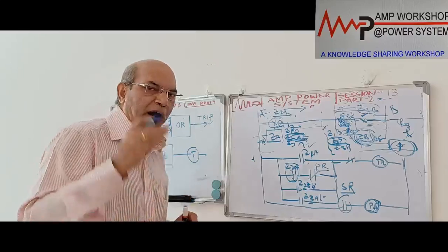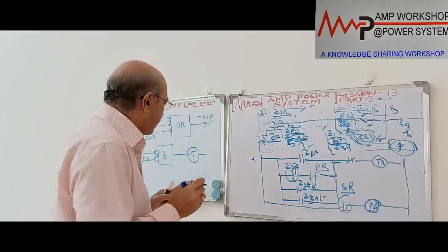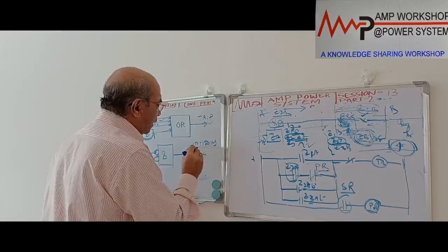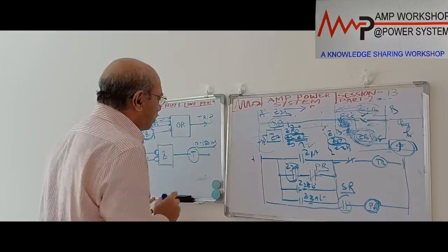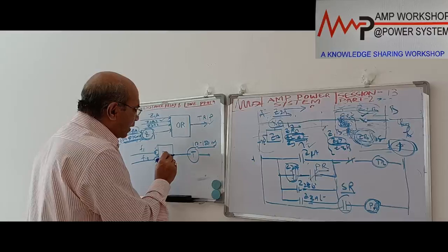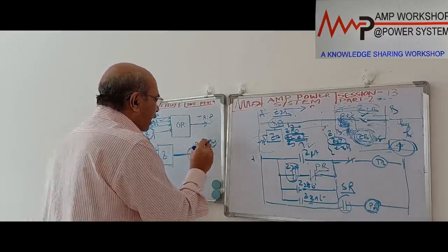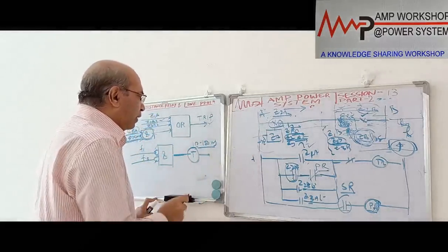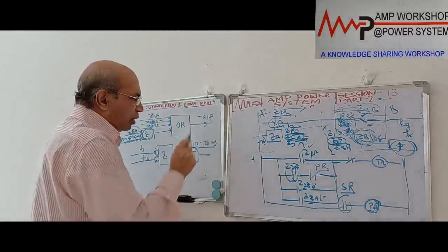And we allow a maximum of 150 milliseconds, generally 100 to 150 milliseconds. It is a 100 to 150 millisecond pickup delay timer. Once the no-signal condition is made, it will energize the timer, but the timer will take 100 to 150 milliseconds to pick up. Within this 100 to 150 milliseconds, if the zone 2 unit is operating, then it will trip immediately.